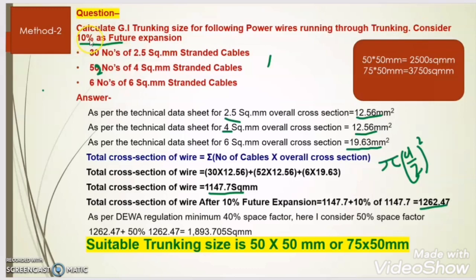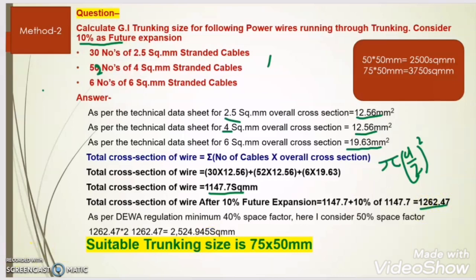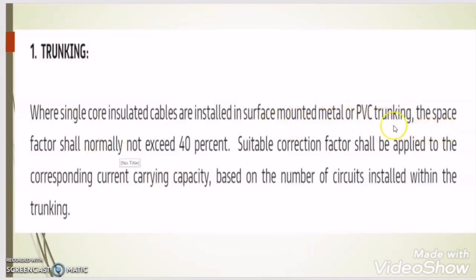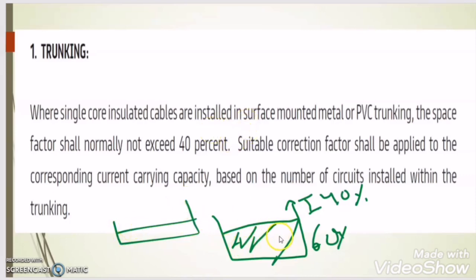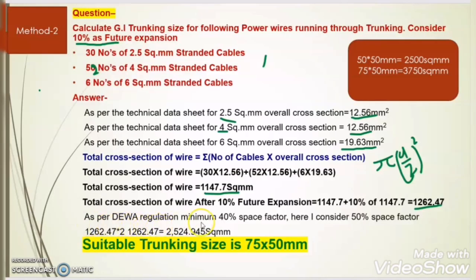As per the question, we have to consider 10% as future expansion. After adding 10%, the total cross section area of wire becomes 1262.47 sq mm. As per the DEWA regulation for metal and PVC trunking, the space factor shall not exceed 40%. This means the trunking should have at least 40% free space. We can go for 50% wire and 50% space, but minimum 40% space is required. Here I consider a 50% space factor, which satisfies the DEWA regulation.